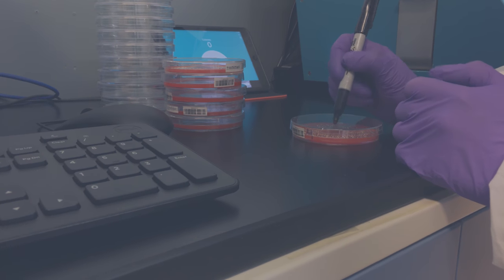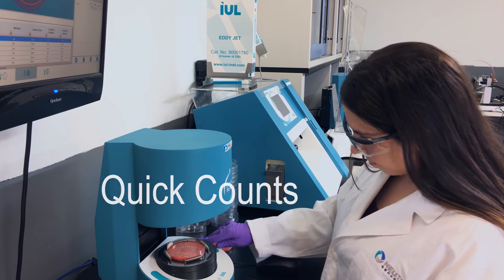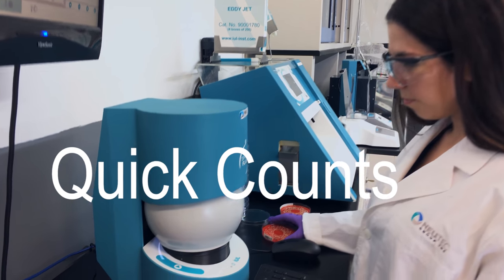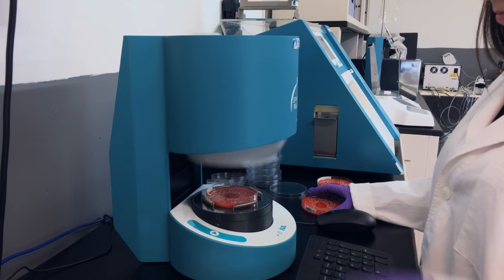The traditional manual method for counting colonies is tedious and time-consuming. It is also subject to human error. The SphereFlash allows its user to easily count a plate every 4 seconds and up to 900 plates every hour.